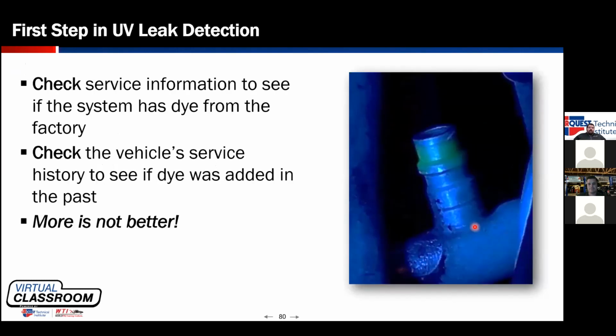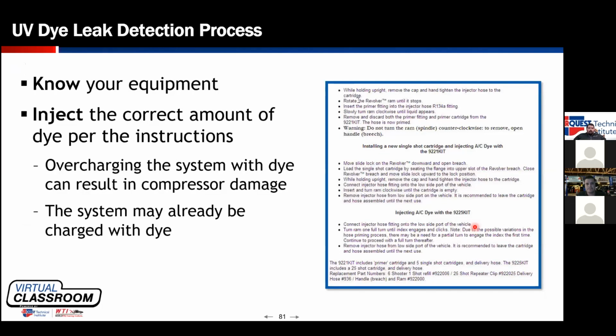If we're going to do dye, our first step with UV dye is to see if we have dye. If we don't have dye, we need to add it. If we do have dye, we don't. Either check service information to see if it's a system with dye from the factory, check service history to see if dye was previously added. Sometimes you can see a residue on a service port, like in this picture, that would indicate that this system has had dye injected and the dye was not cleaned off of the service port. Again, know your equipment, putting the correct amount of dye in, and make sure that the light that you have works with the dye that you have.